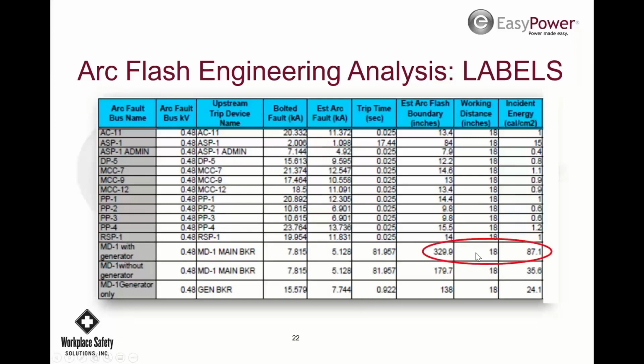So here's the problem. This one is 480 volts, main distribution panel with a generator. It's a 329-inch arc flash boundary, 87 calories. That's what's going to be on the label. So you start looking into this a little further. You look at trip time, 81 seconds. In reality, the 1584 standard says you can use the default 2-second trip time when you have these very long trip times.